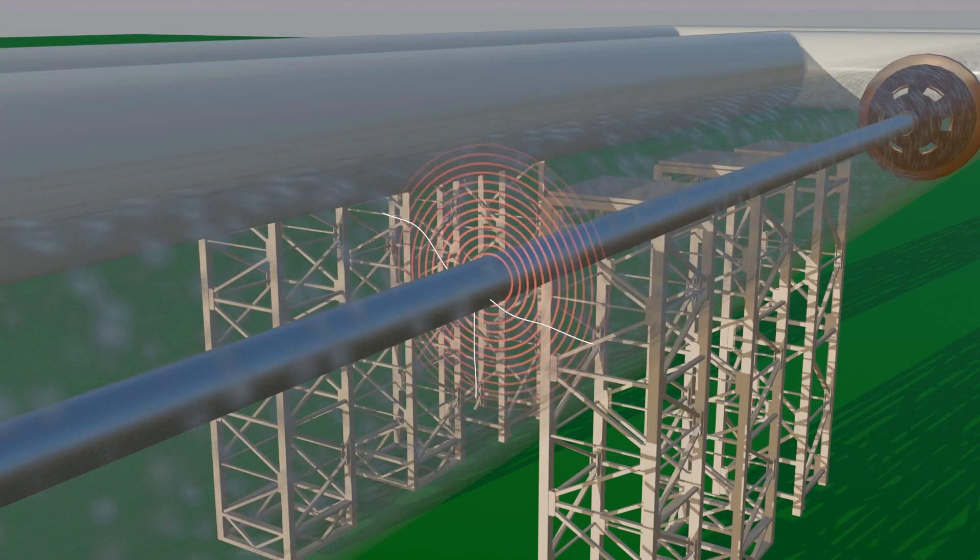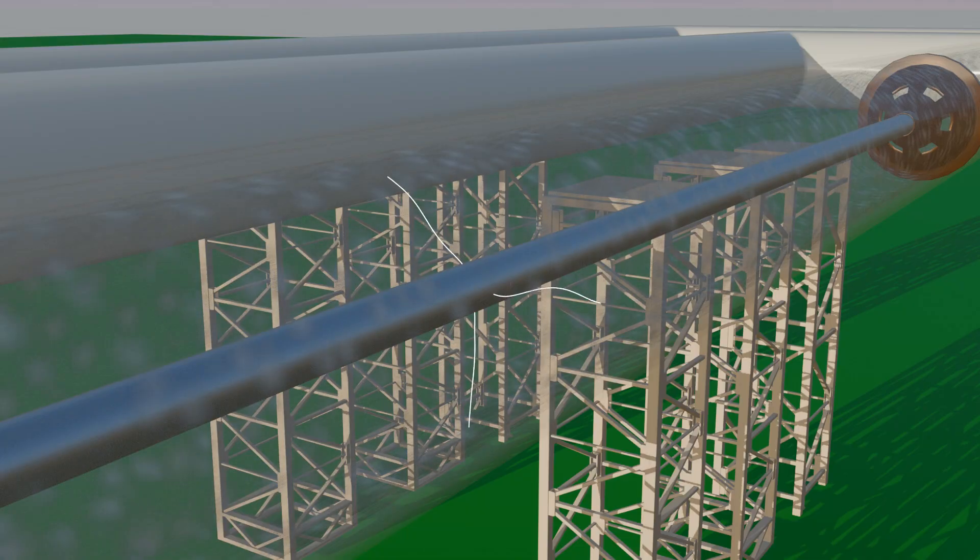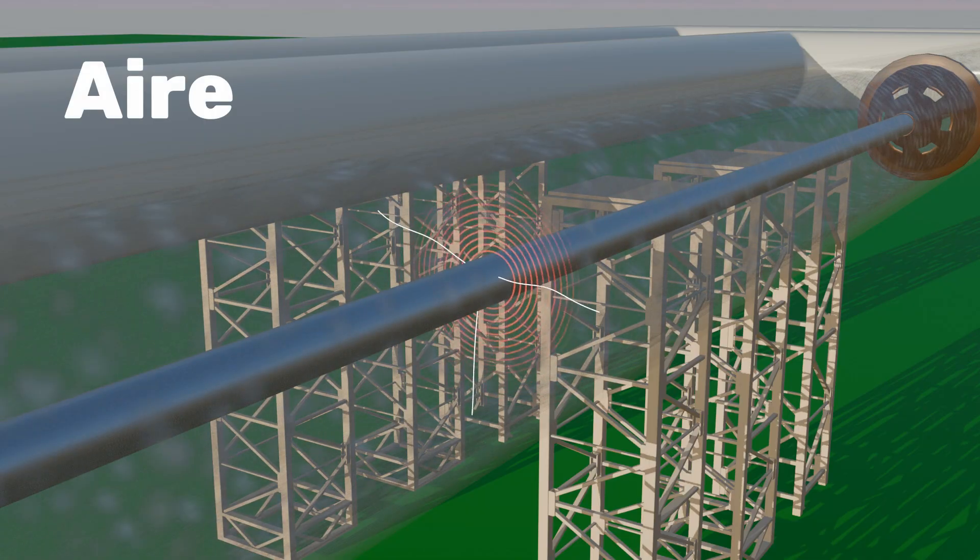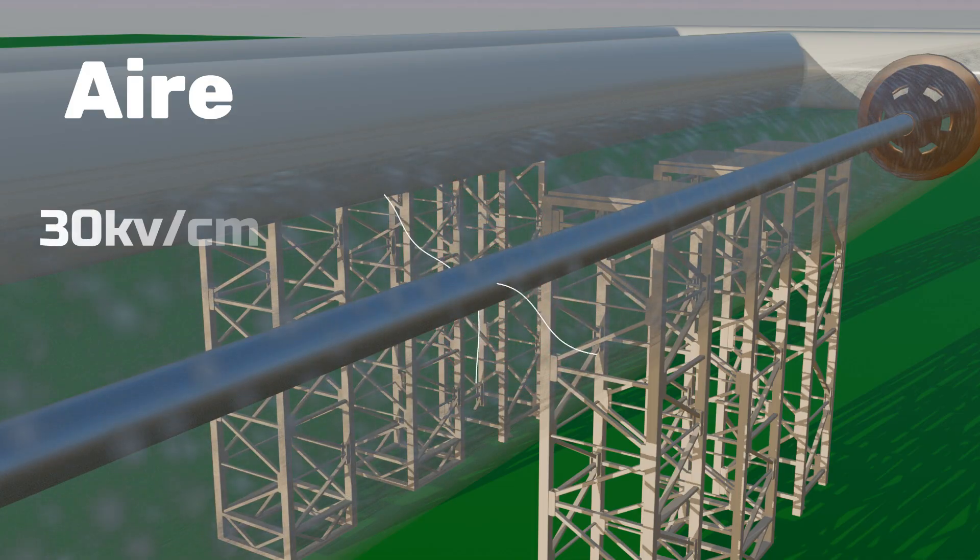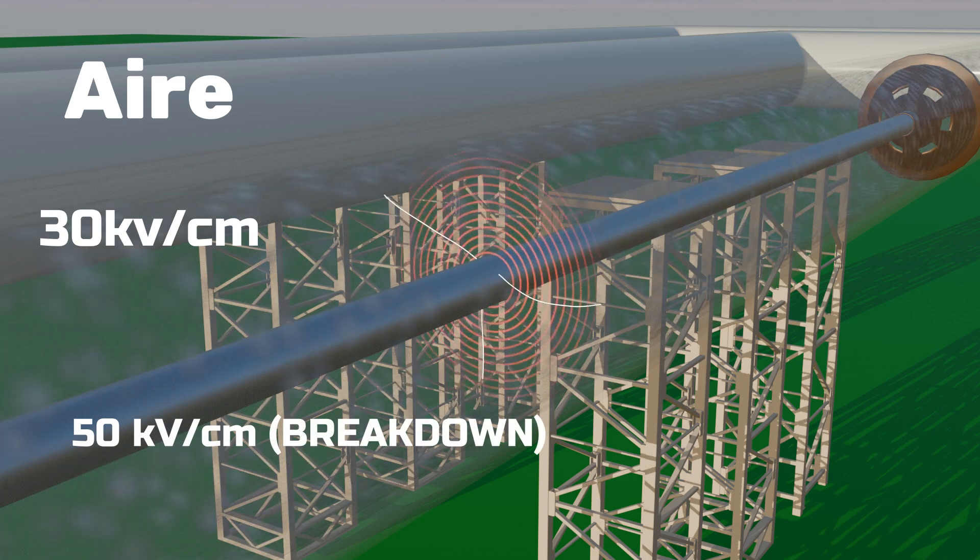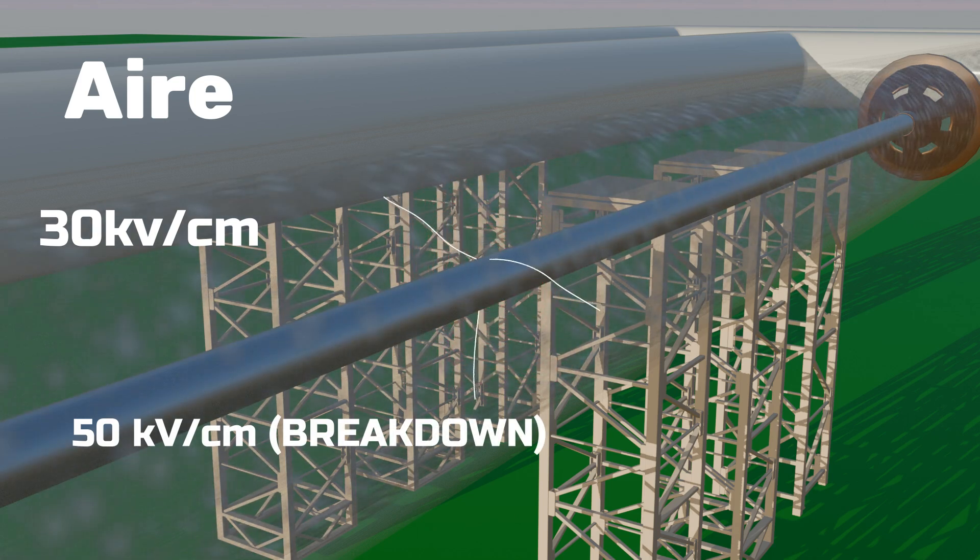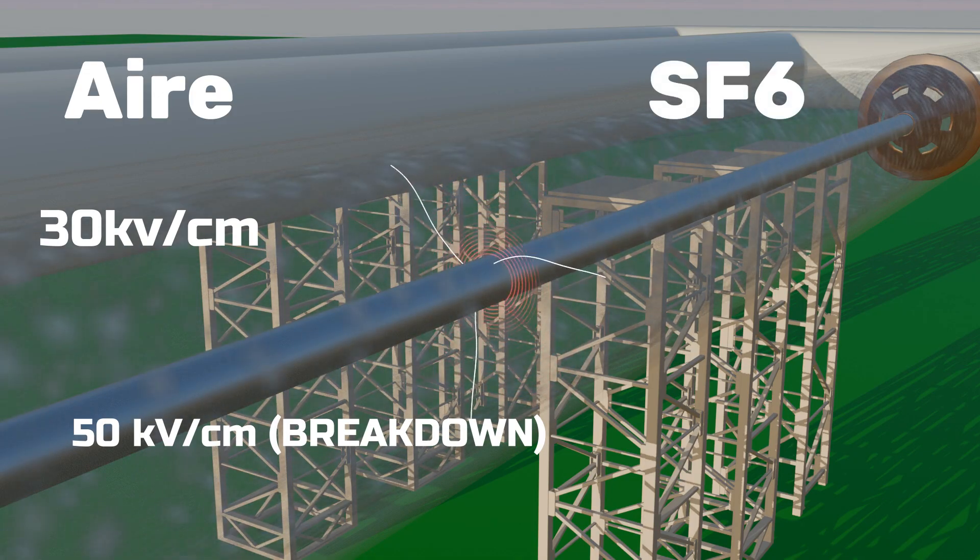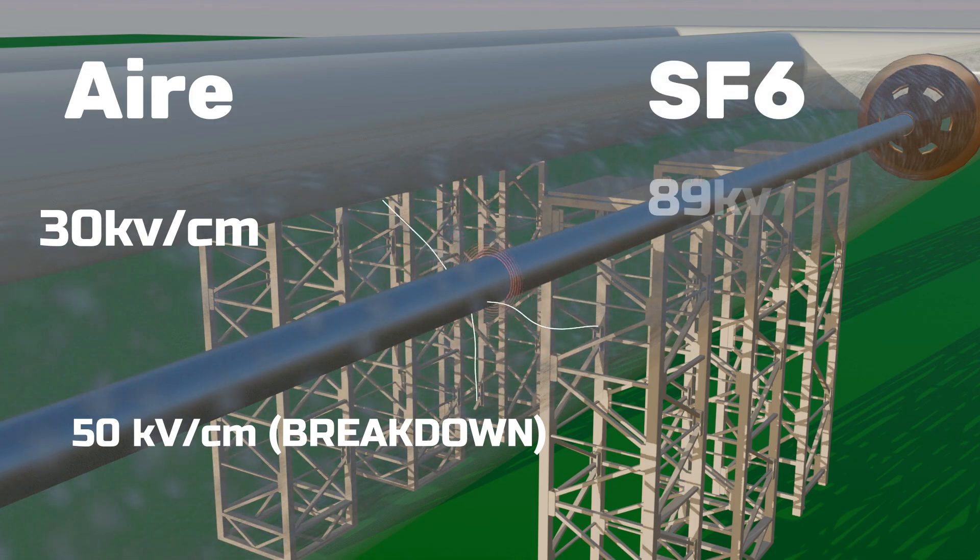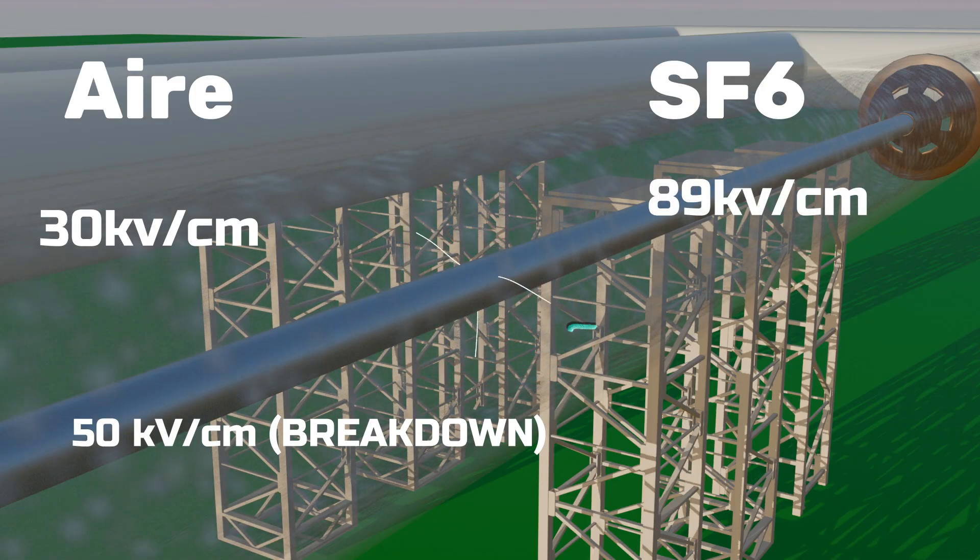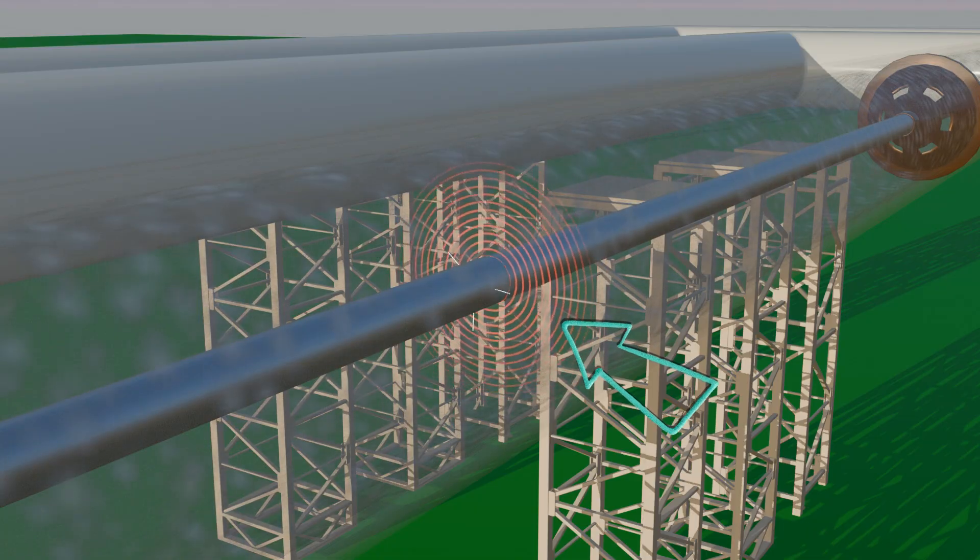But here, the SF6 gas filled inside has a dielectric strength almost three times higher than that of air. Let us simplify this: air has a dielectric strength of about 30 kV per centimeter, so if we apply around 50 kV per centimeter, air starts behaving like a conductor. In comparison, SF6 gas has a dielectric strength of about 89 kV per centimeter, nearly three times higher. As a result, its particles become less ionized, reducing the chances of breakdown.